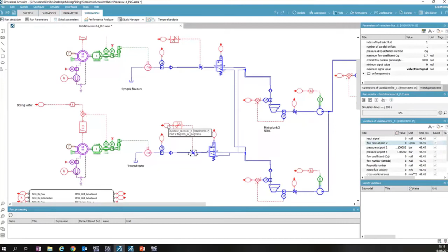The signal to open or close this valve is coming from the PLC. I'm going to plot what the PLC is sending us. As you can see, the PLC is completely opening the valve because the set point was set to 200 liters per minute, and the closed loop feedback is not reaching 200 liters per minute, so it's opening the valve completely.